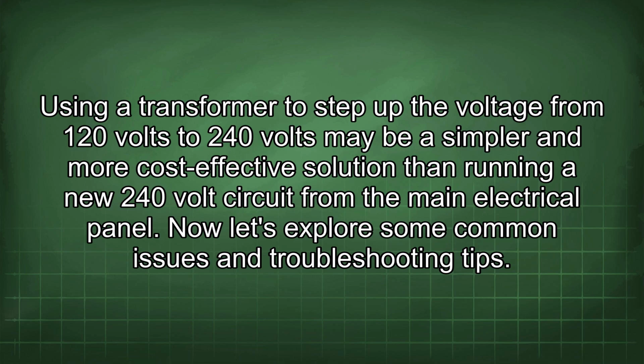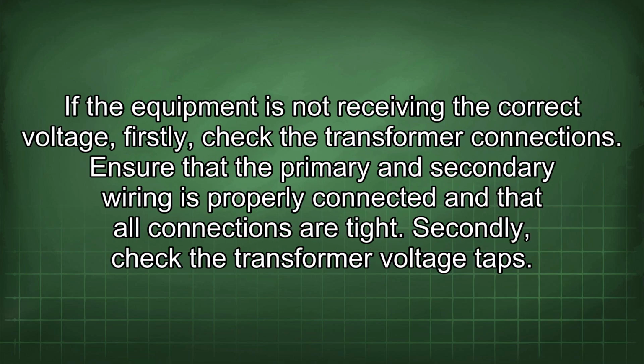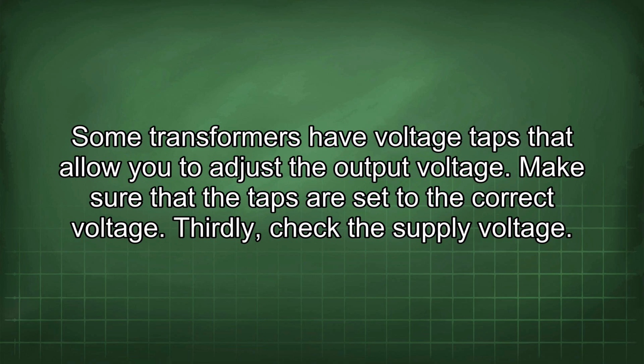Now let's explore some common issues and troubleshooting tips. If the equipment is not receiving the correct voltage, firstly check the transformer connections. Ensure that the primary and secondary wiring is properly connected and that all connections are tight. Secondly, check the transformer voltage taps. Some transformers have voltage taps that allow you to adjust the output voltage. Make sure that the taps are set to the correct voltage.